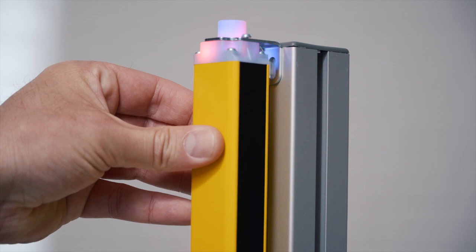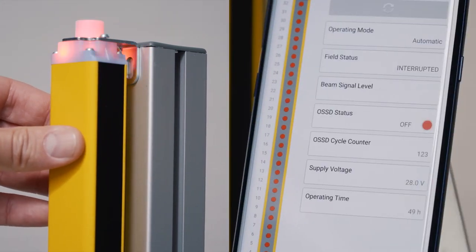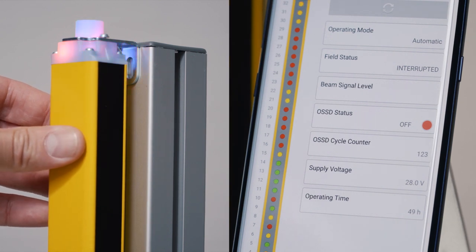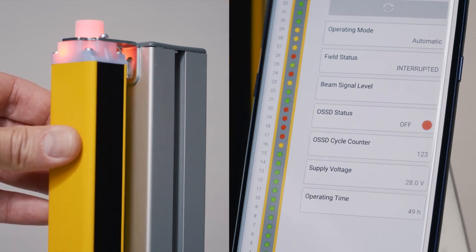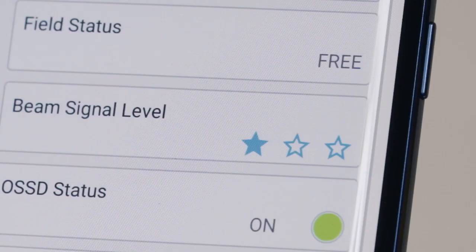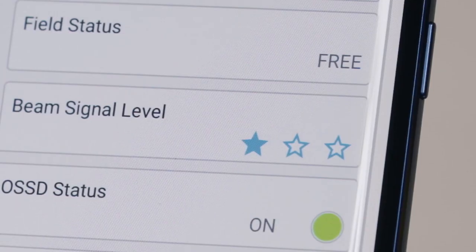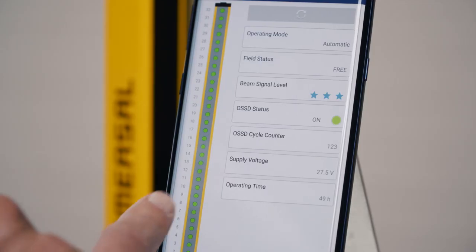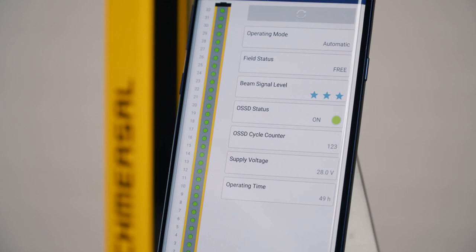For the alignment of the light curtain the diagnosis app gives you very useful information. When you align the light curtain there is not only the display of the general signal strength, there is also the display of each individual beam and its signal quality. One star means that the quality of the alignment is not good; three stars indicate when the alignment is perfect. This is also shown with a green light at all light beams.